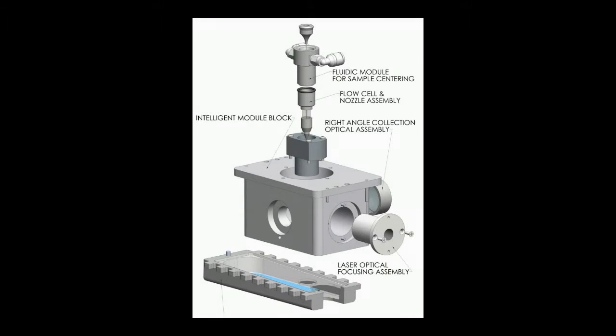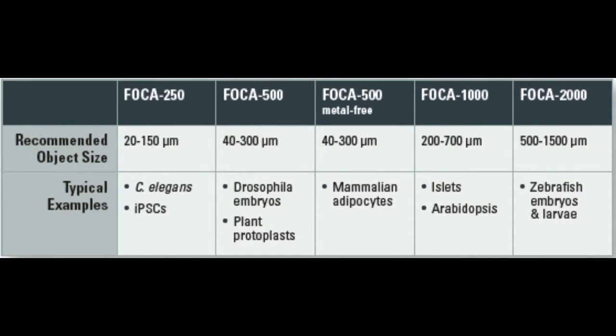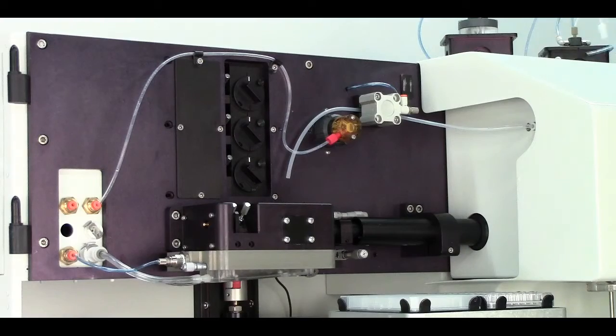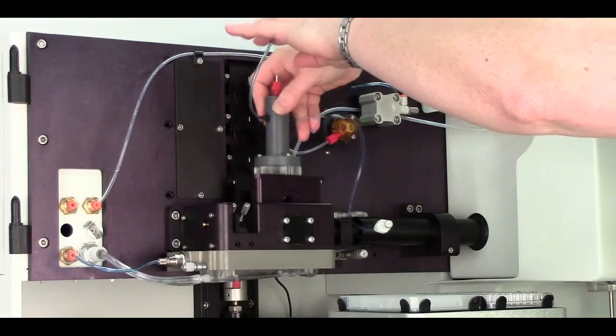Each FOCA module is a precision assembly of fluidics flow cell and its corresponding pre-aligned optics contained in a single swappable module. Each FOCA specializes in a subsection of the sample size range, but an operator can quickly and easily change FOCAs being used for various sample types. Additional FOCAs can always be added later, as the need arises.